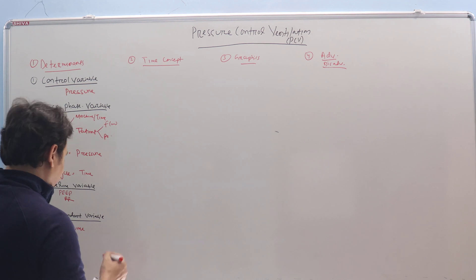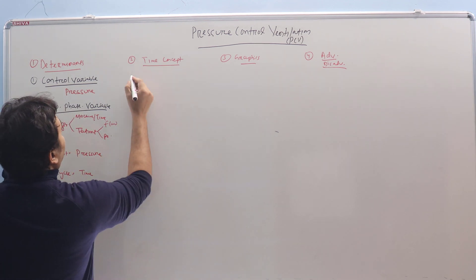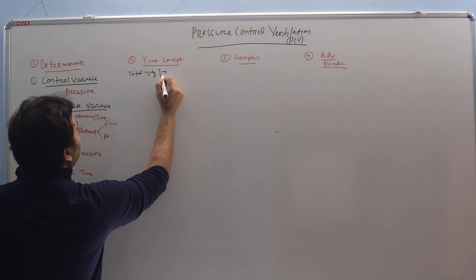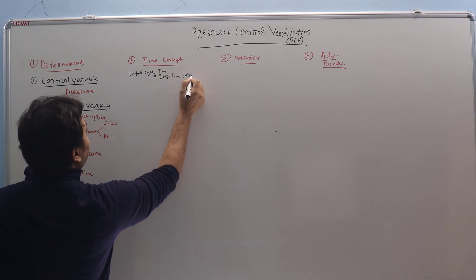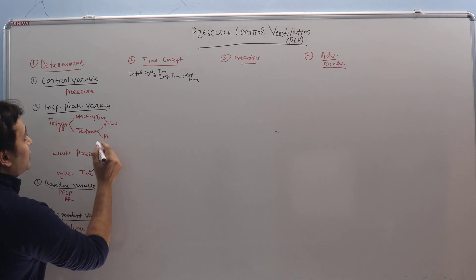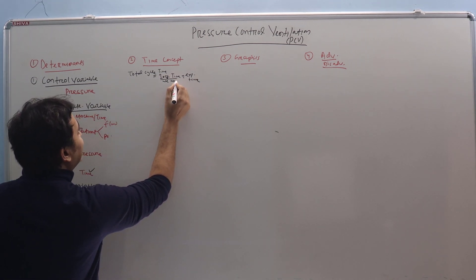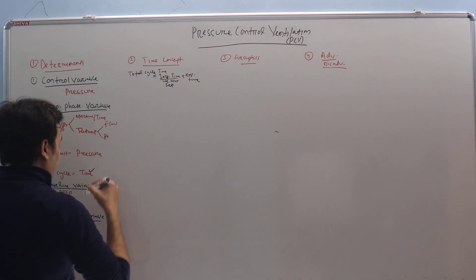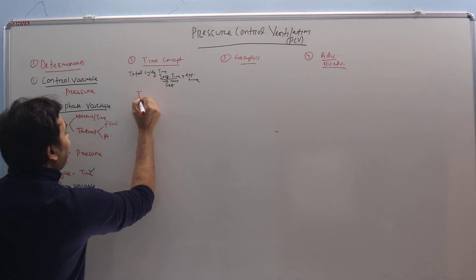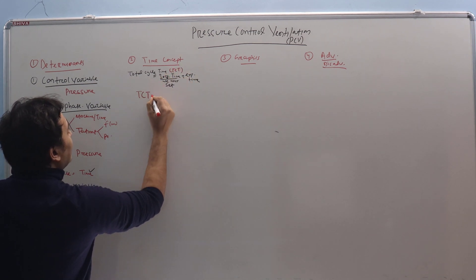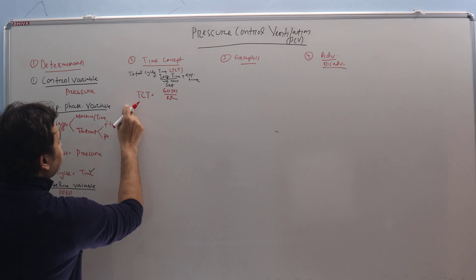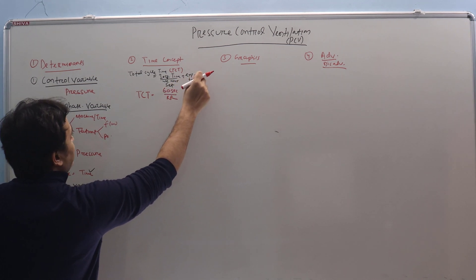Coming to the Time Concept: the total cycle time is equal to Inspiratory Time plus Expiratory Time. We have already selected the Inspiratory Time — it is constant. So if you want to increase the expiratory time, you just reduce the respiratory rate. Total cycle time is 60 seconds divided by respiratory rate. So if you decrease the total cycle time while Inspiratory Time is fixed, the I:E ratio will automatically change.